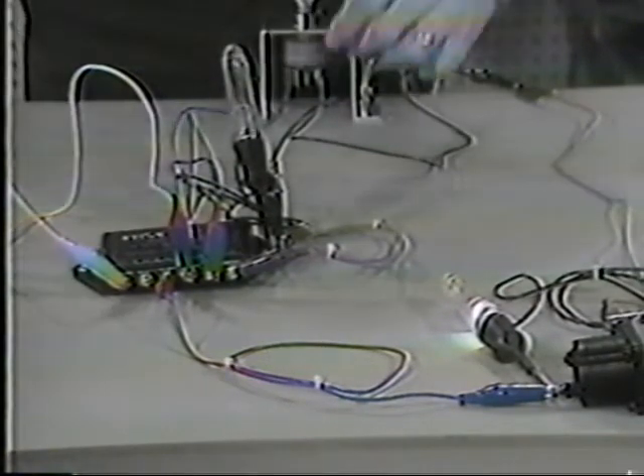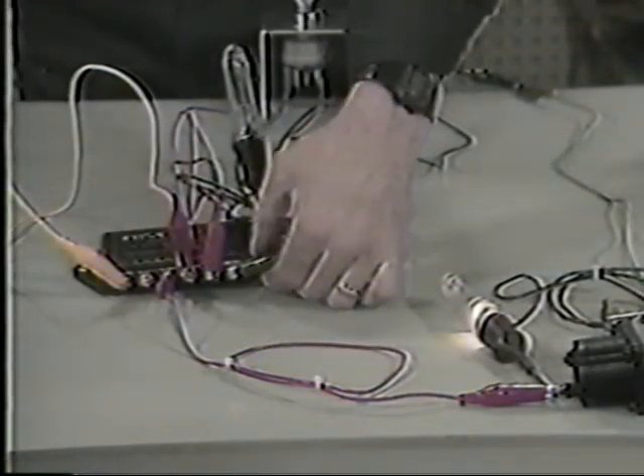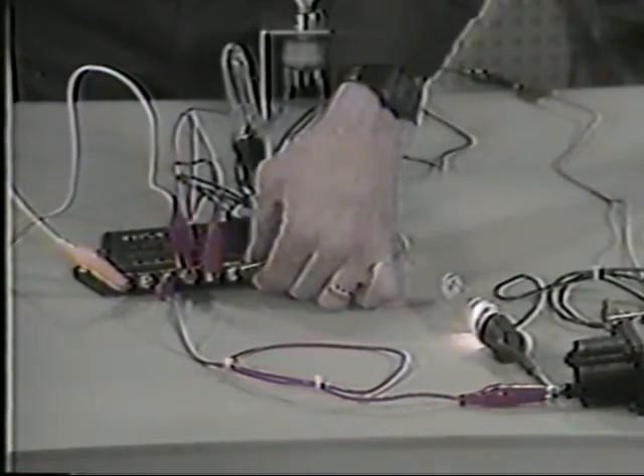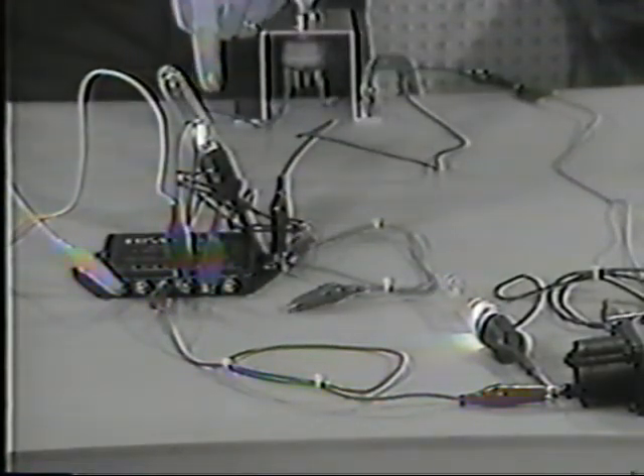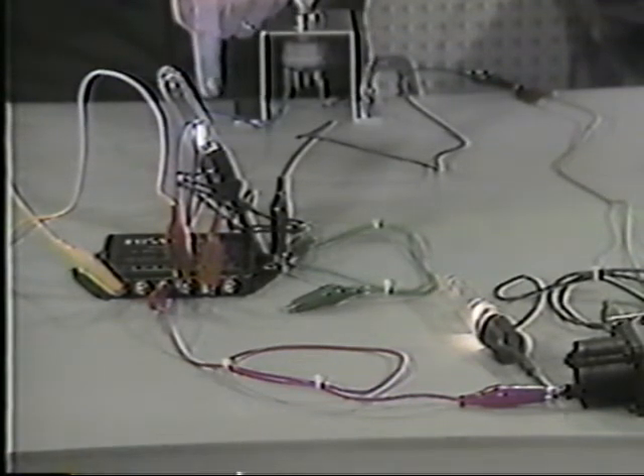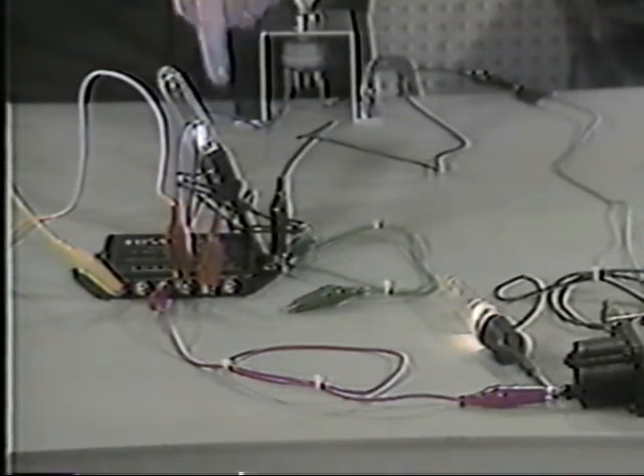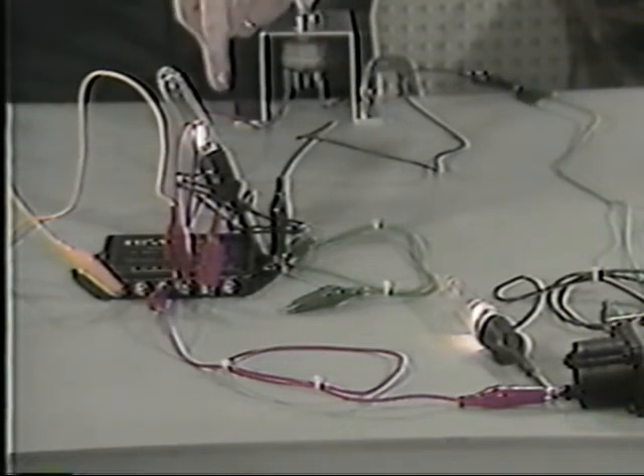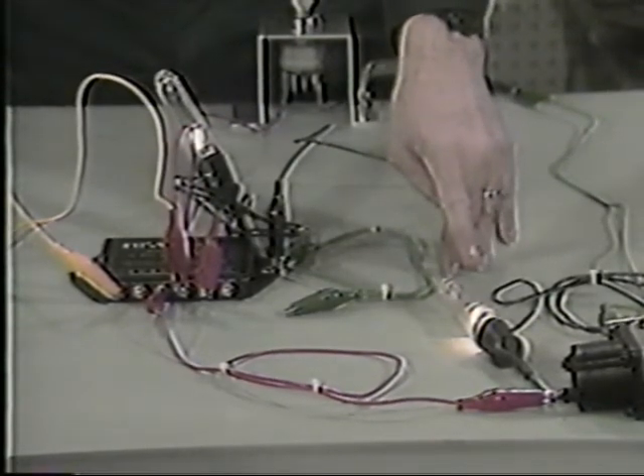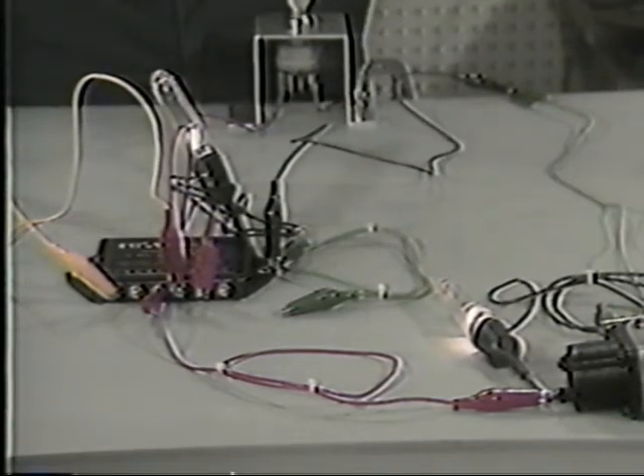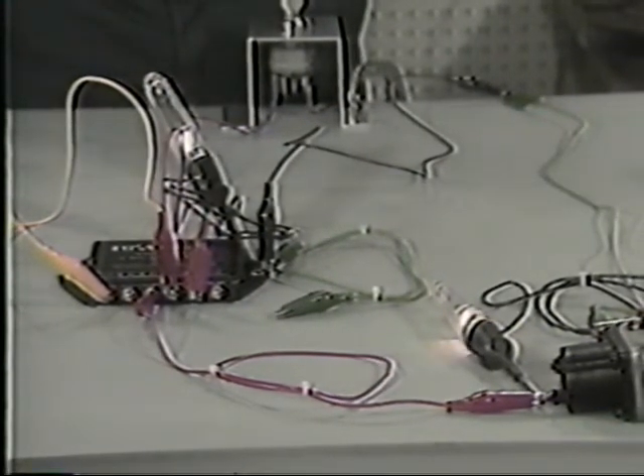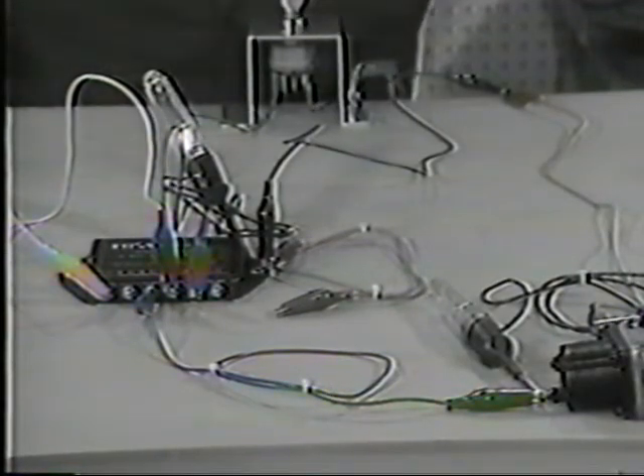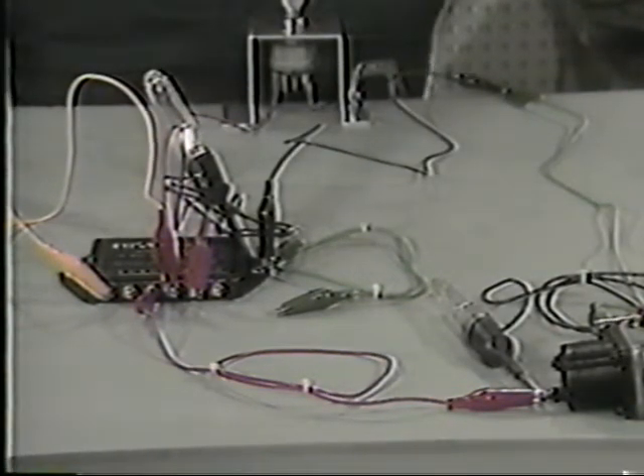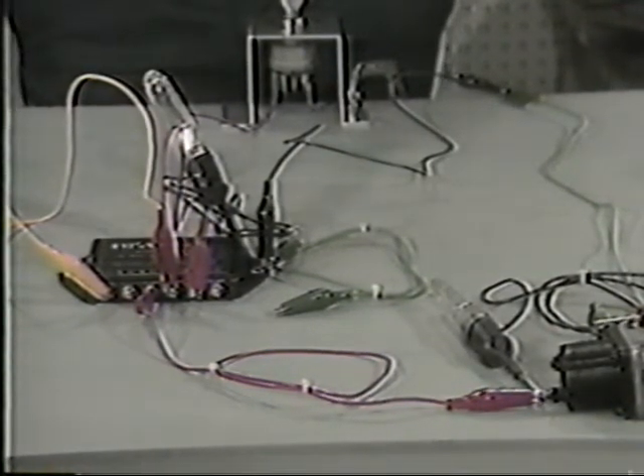Last test, remove the jumper wire to ground from post number 6. The test light that's connected to post number 5 should turn on, simulating a low water alarm. Approximately 30 seconds after this happens, this test light should go out and the fuel solenoid should turn off. A module that doesn't pass any of these steps has a problem and should be replaced.